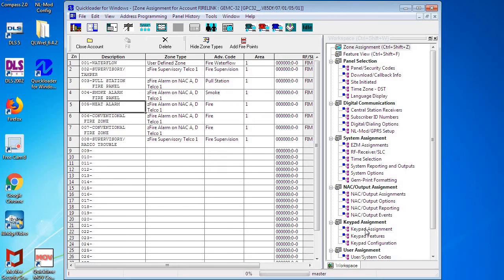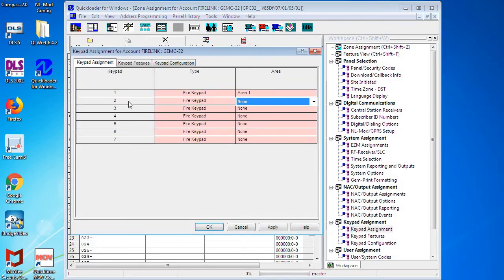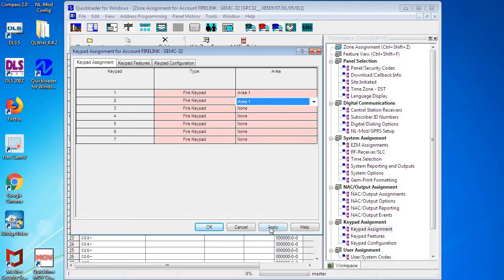If we were going to add a new remote enunciator to the system, that would be done in Keypad Assignments by taking number two address and setting it to Area One. And you would also have to then address the other remote enunciator as keypad number two, and that's explained in another video—we'll also post that link below.